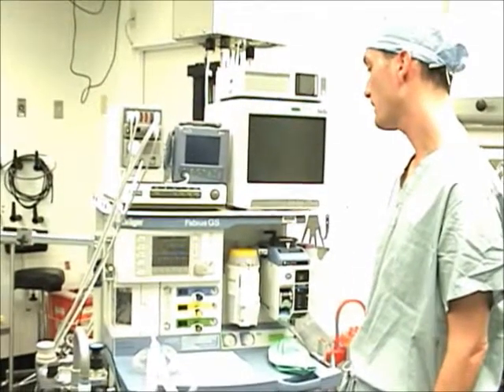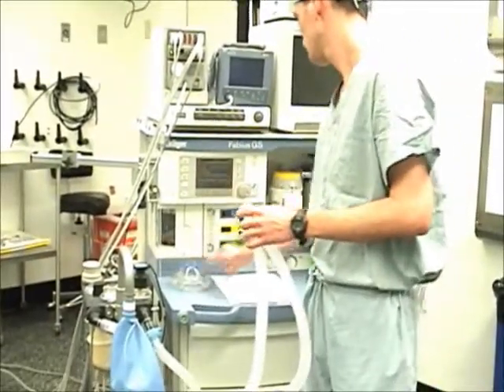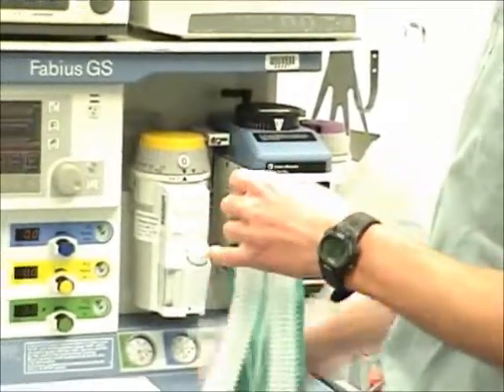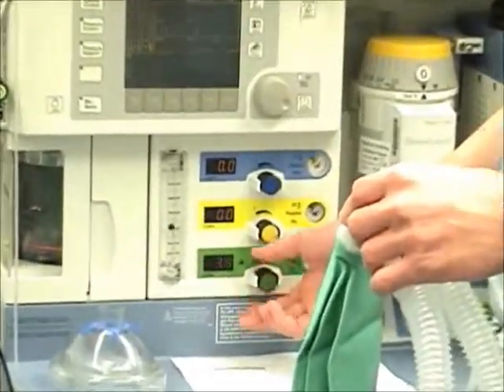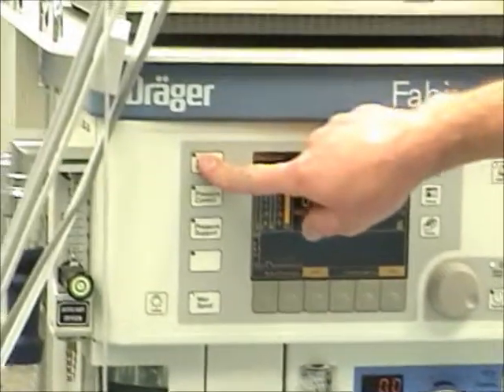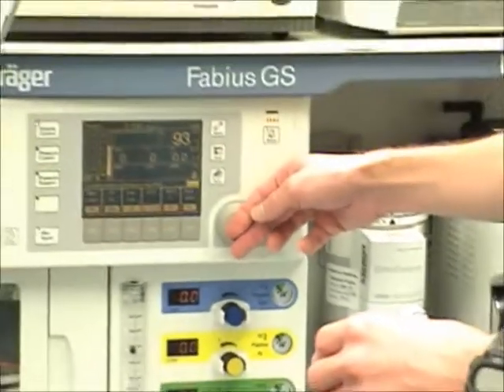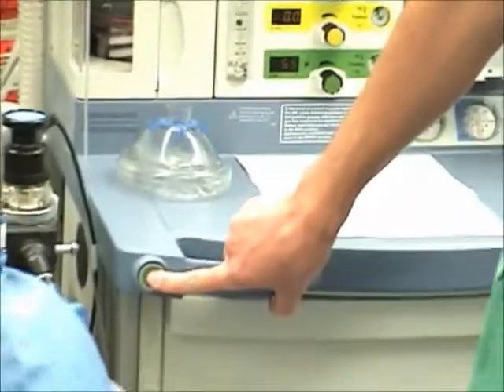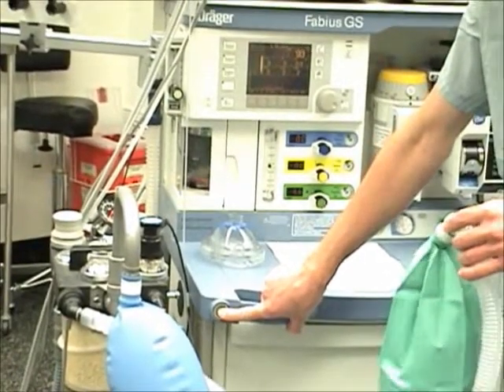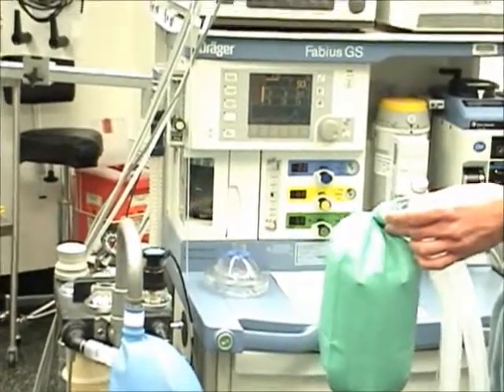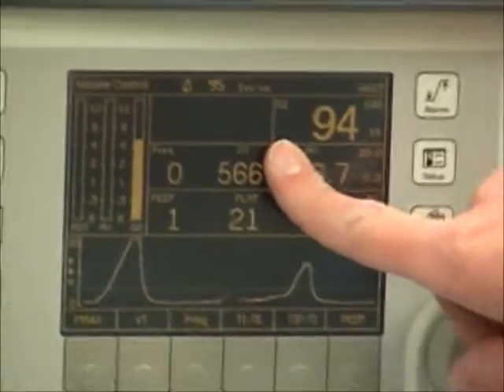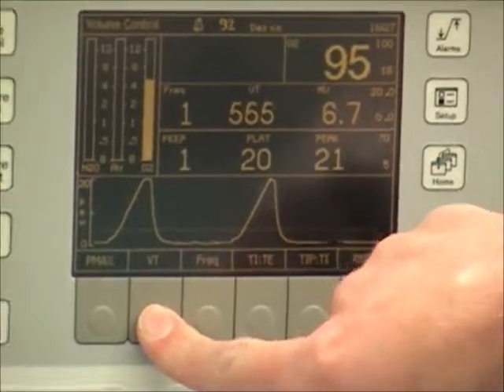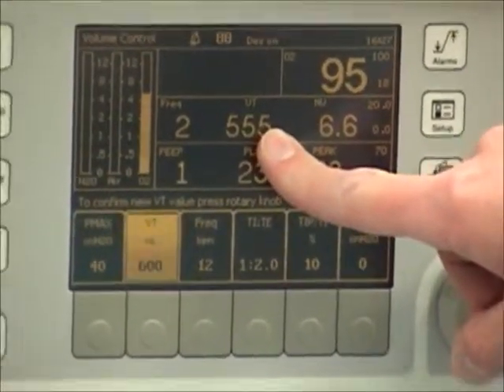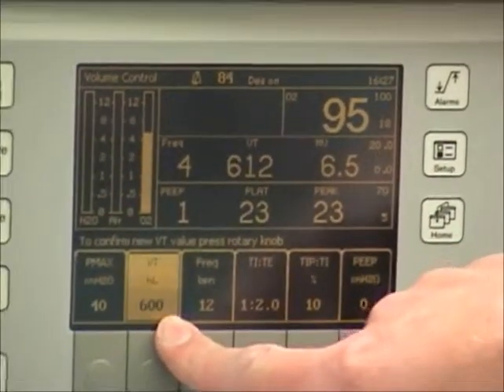To check ventilator operation, connect a breathing bag to the Y piece to act as a test lung. Set the oxygen metering valve to 5 liters per minute. Select the volume control soft key and confirm the selection by pressing the rotary dial. Fill the bellows by pressing the O2 flush. Check that the tidal volume delivered is approximately equal to that set in ventilation parameters. Tidal volume delivered 565, preset tidal volume 600. Observe the proper function of the inspiratory and expiratory valve discs.